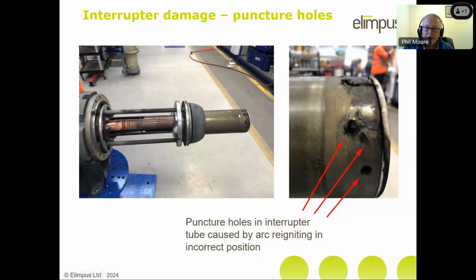If we just have a look at the end of this interrupter tube here, you can see these great big holes in the glass fibre, and this is caused by the arc reigniting and blasting a hole straight through the glass fibre, and instead of going through the contact, it's probably making contact with one of the metal parts inside the circuit breaker. Now, bear in mind what I said earlier, all of these breakers actually have 2 breaks per phase, so having one break doing that isn't ideal, but you'll still be able to recover from it. If you have 2 of these doing it simultaneously, you're probably in a failure situation. So this is a very poignant example of why this monitoring was so effective. You can actually see on this one, it's punctured such a large hole that little bits of the glass fibre are sticking out proud from the surface. There you go.